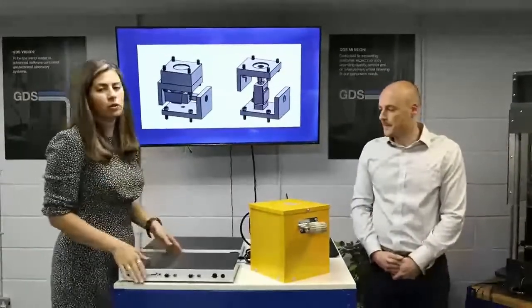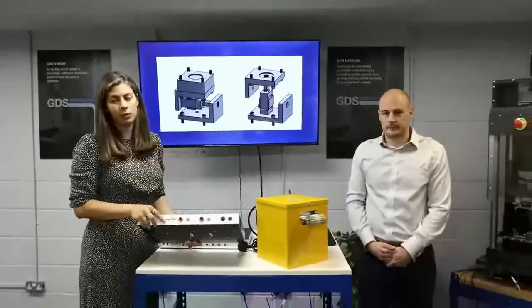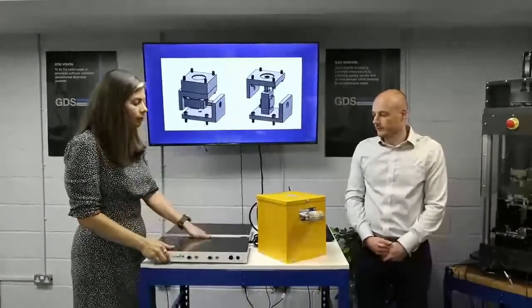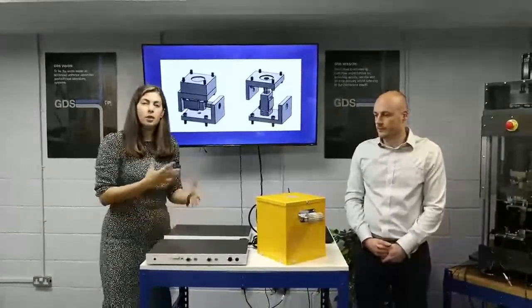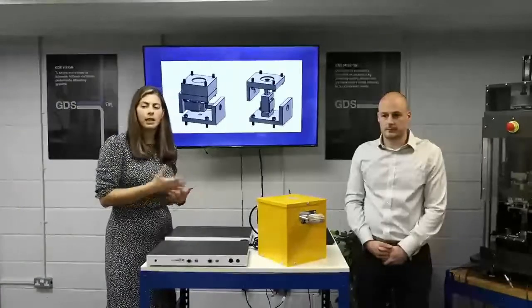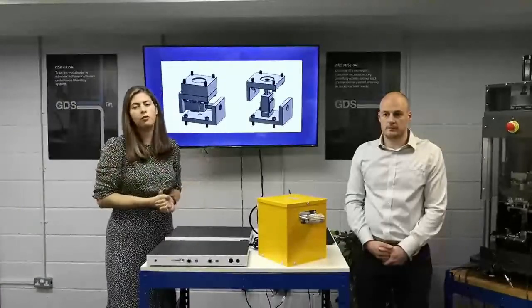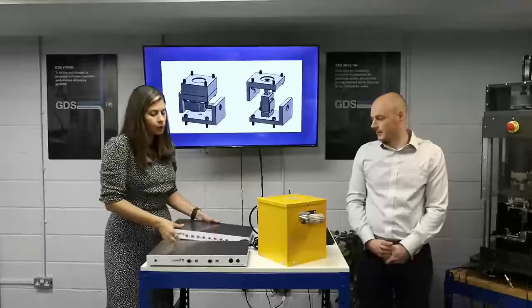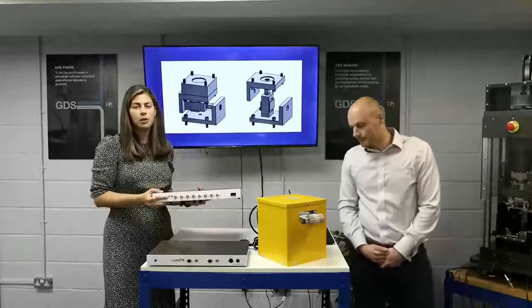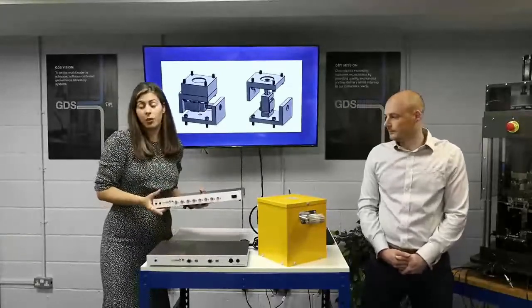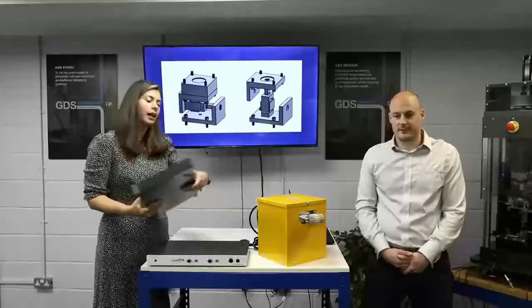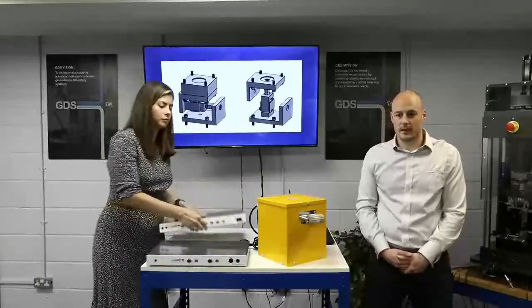On this system we've got two channel LVDT signal conditioning boxes. The standard configuration is one box. If you add on the horizontal LVDT, that box expands to 3 channels. This is our control box, the advanced DCSS box, which has 8 channels.